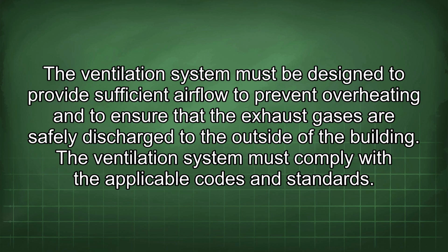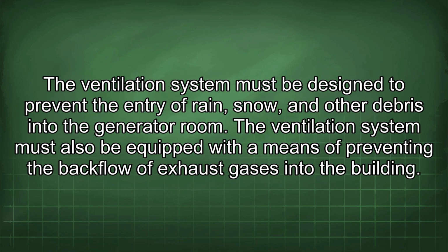The ventilation system must comply with the applicable codes and standards. The ventilation system must be designed to prevent the entry of rain, snow, and other debris into the generator room. The ventilation system must also be equipped with a means of preventing the backflow of exhaust gases into the building.